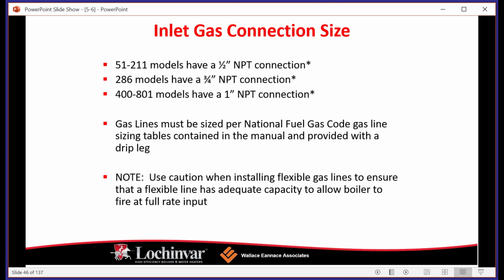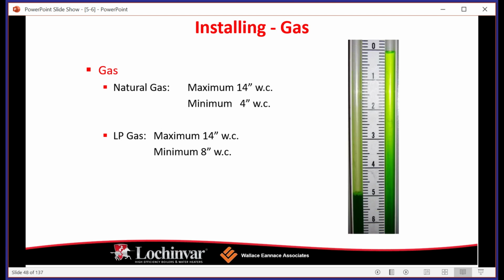However, if you don't have a properly sized gas line to a boiler, it's going to result in a lot of issues, and you're not going to be able to get your maximum BTU input. So you may have an example where a boiler will fire, but it's not firing efficiently, or you're potentially having faults, things like that. That can be due to improperly sized gas lines. Again, the National Fuel Gas Code book is very important. And read the manuals. All this information is explicitly called out for each individual piece of equipment that you buy. And if you have questions on any of this, particularly gas, venting, install, you can reach out to Wallace Eannace and we'd be happy to help walk you through it.